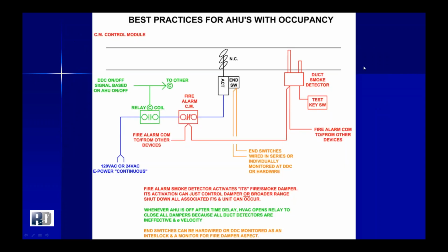But using, again, our same basic diagram, we do have the duct detection that has a control module within close proximity of the fire smoke damper itself. But in very close proximity to that, there is a control relay that is in series with the power connection. Whenever the HVAC system were to go off for whatever reason, that relay could be made to open and in turn tell the fire smoke damper to close. This can be a system that could be wired 120 volt by the electrician. It could be wired 24 volt by the control contractor, but the main purpose of that is that the power feed to these relays would be a continuous power source.